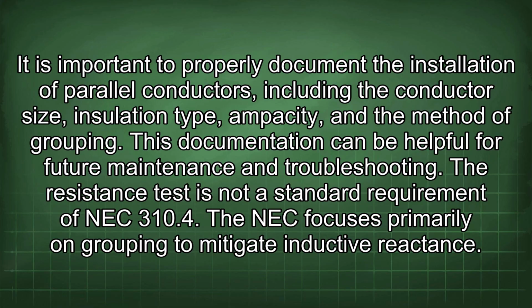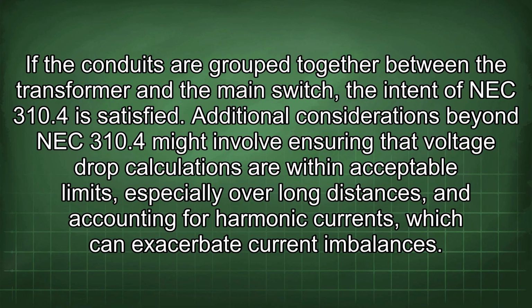The resistance test is not a standard requirement of NEC 310.4. The NEC focuses primarily on grouping to mitigate inductive reactance. If the conduits are grouped together between the transformer and the main switch, the intent of NEC 310.4 is satisfied. Additional considerations beyond NEC 310.4 might involve ensuring that voltage drop calculations are within acceptable limits, especially over long distances, and accounting for harmonic currents, which can exacerbate current imbalances.